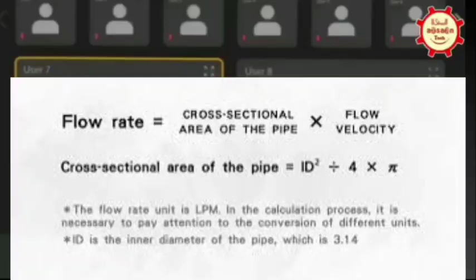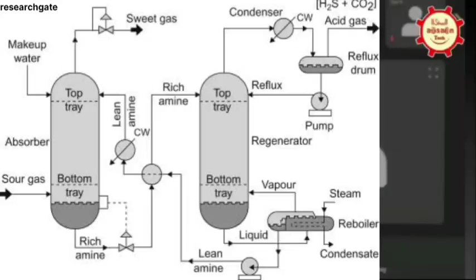The fluid with high velocity will cause erosion corrosion. For gas, it is very high, like 20 meter per second or sometimes 30 meter per second. So the velocity is decreased by increasing pipe size, or it is limited by the pipe size. Velocity is very important to control the erosion corrosion, and we have to design the pipe as per API RP 14E erosional velocity limit. So that's why velocity comes into the picture.